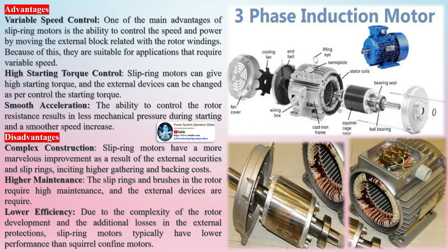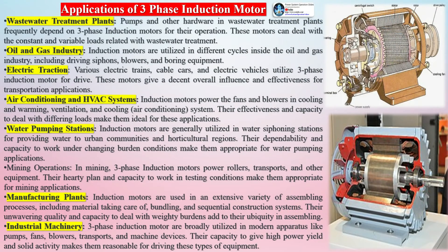Disadvantages of slip ring motors include complex construction due to the external resistances and slip rings, leading to higher assembly and maintenance costs. The slip rings and brushes in the rotor require high maintenance, and the external devices are an additional requirement. Due to the complexity of the rotor construction and additional losses in the external resistances, slip ring motors typically have lower efficiency than squirrel cage motors.